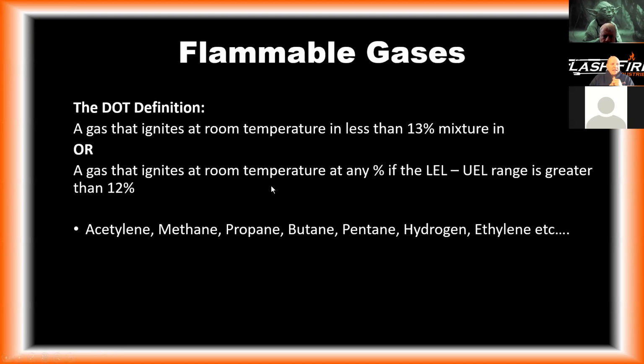All right, so flammable gases is the other way we can die, right? So again, driven from industry, DOT, Department of Transportation, what is the actual definition of a flammable gas? It's got two options: a gas that ignites at room temperature in less than a 13% mixture, meaning the LEL, the lower explosive limit in air, is less than 13%, or a gas that ignites at room temperature at any percent if the LEL and UEL range is greater than 12%.